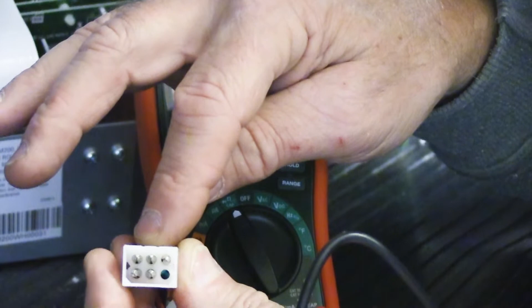How do I know that? Well, you have to backtrack what happened. Something happened in the master station when Rocky was messing around with it, and it caused some sort of problem. What that problem may or may not be, I can't tell you because I've never seen the set, but whatever the problem was, it was heavy duty enough that it blew the fuse in the transformer.